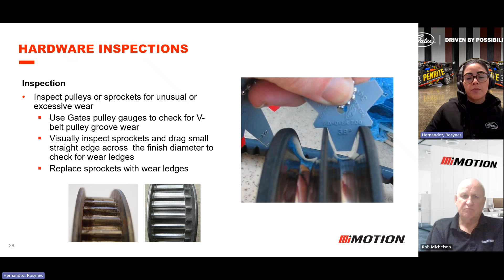Generally, the drive pulley is the small one. In most cases it is a slow-down drive, so it will be the smaller pulley that you check more regularly than the larger pulley. And I think traditionally it is about every three times you change your belts that the smaller pulley is more likely to need replacement as well. Yes, correct. In general, but again, it depends on the speed, whether you have the proper tension, and whether you have the proper alignment of the pulleys. If you don't have these, the pulley will probably have problems.